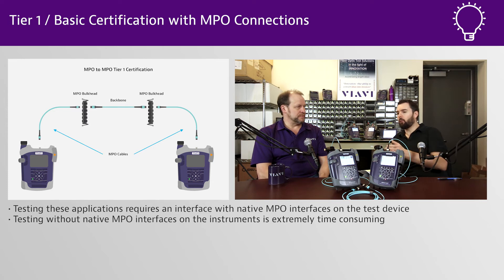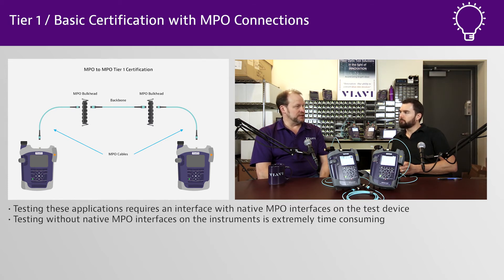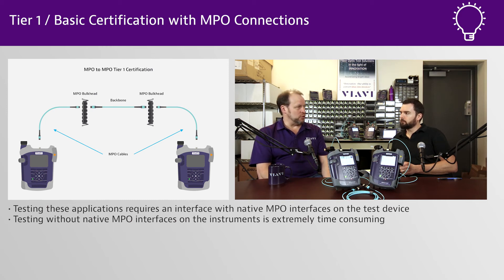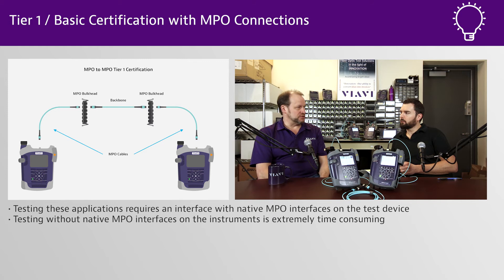This is more prevalent when you get into 40 gig and 100 gig with QSFPs, where you've got a direct QSFP or MPO connection into your switch and servers. Your link itself, instead of being a duplex LC, is a 12-fiber MPO — and that's why you need to test that link with native MPO testing. You can also test the channel by disconnecting from the QSFP plugged into the switch, server, or router and then testing the channel.